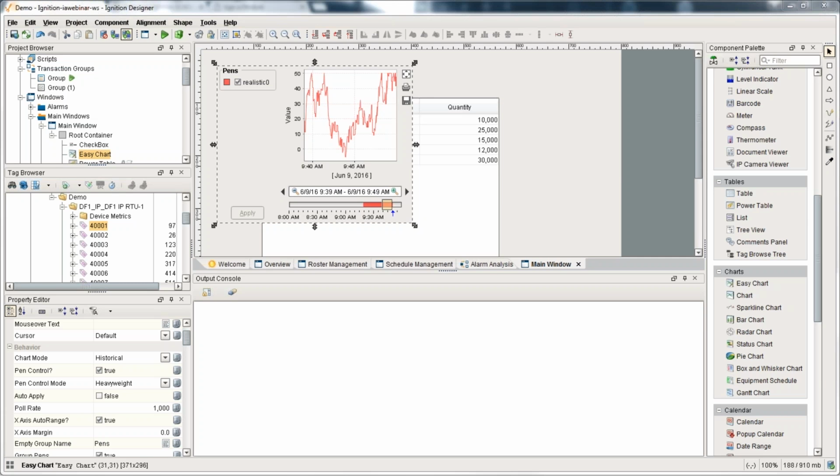Without the tag historian, we don't keep any historical data. So Ignition, when you just connect up to a device and view the information, it's live data. If we don't log that data to a database, then we're not going to track that history. As soon as you log it to a database, it could be a local MySQL or whatever, then you have the information. Then you can have it store as much as you want, essentially.